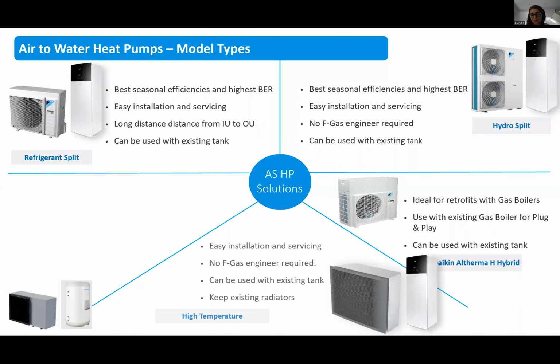Another unit that we have for retrofit would be a high temperature system. So the high temperature is a direct replacement for oil and gas boilers in that it will give you up to 70 degrees of a flow temperature. It's a hydro split, so it's a water connection between the indoor and the outdoor unit. They work really efficiently at very low outdoor temperatures because they're really designed for the Nordic regions where they have prolonged minus temperatures. Not something that we really get here in Ireland. So we haven't really found an area of the market that it really suits.